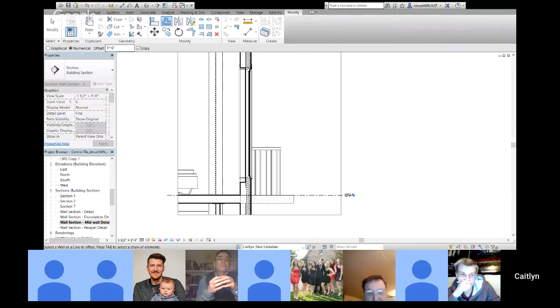So that means you might have a little bit of a drop soffit there where your cursor is, and then it would resume to be 9 feet beyond that, assuming all the beams in the building are that depth, or all the beams that move through those residential units are that depth. And again, that could be a point for air supply because it helps make up for the losses by the window, and keeps the duct out of the other portions of the space. Does that make sense? Yeah. And that gets back to the point we made last time about how you can consider the HVAC duct placement in a way that creates something in the space rather than compromising the ceiling height.